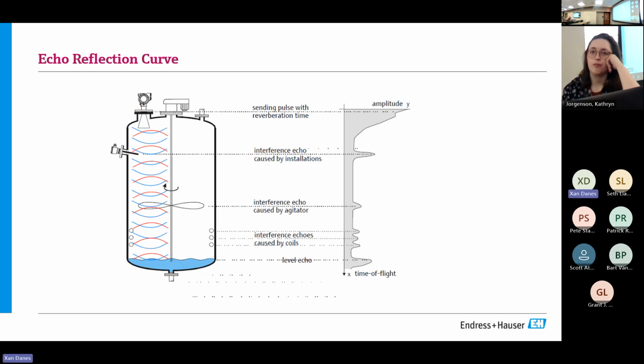If you look back at some of the old training materials, we'd show things like this, where we've got our radar generating its pulse. My plot on the right is rotated 90 degrees to the left, but you can see the amplitudes in this hypothetical example. I see some amplitude off the level switch, some off the agitator. Down near the bottom, I can see signal amplitude off my heating coils. And all the way down at the bottom, I see another little hump where my level echo is.